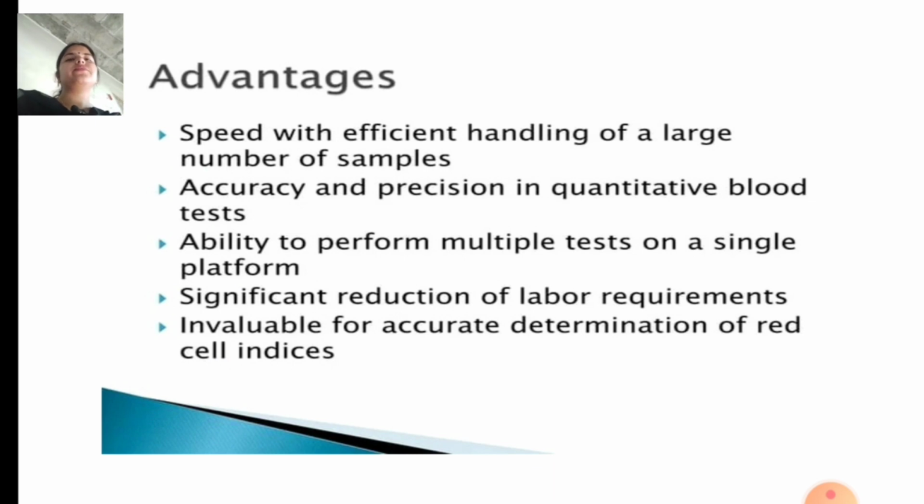Now the advantages of automation in hematology: speed with efficient handling of a large number of samples, accuracy and precision in quantitative blood tests, ability to perform multiple tests on a single platform, significant reduction of labor requirement, invaluable for accurate determination of red cell indices.